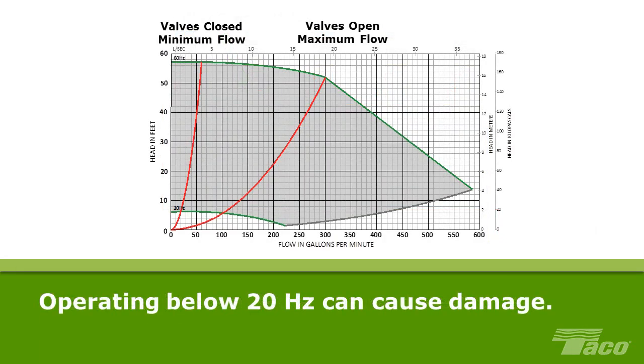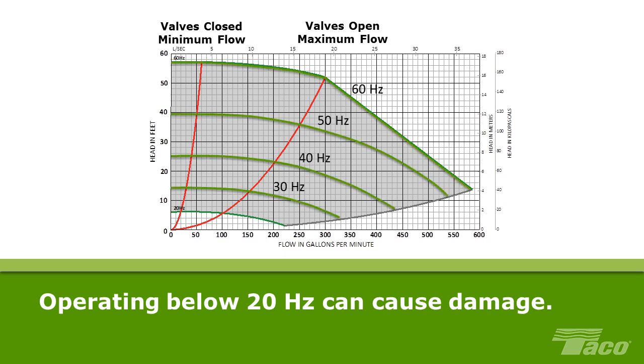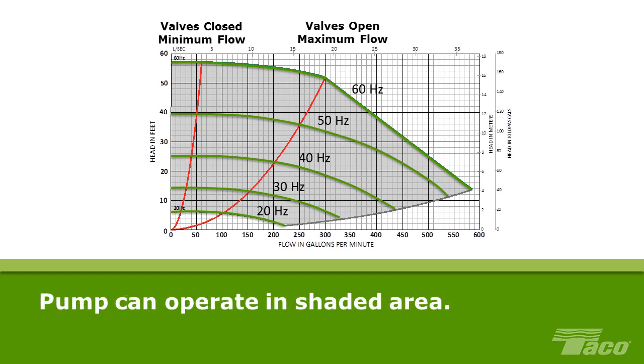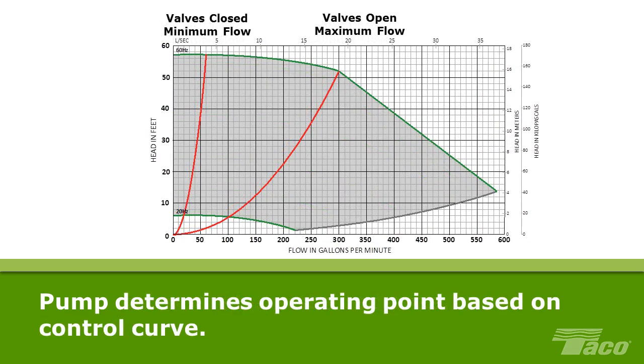Now, let's overlay the performance curves of a self-sensing pump at 5 speeds, from 60 Hz maximum speed to 20 Hz, the minimum speed. Operating the pump below 20 Hz may be detrimental to the mechanical seal and is not recommended. Therefore, the pump is programmed not to operate below this point. The pump can operate anywhere in the shaded area, but it must determine exactly at which point to operate in order to satisfy any given system demand. The pump determines that actual operating point minute to minute based on a control curve drawn for each pump individually.